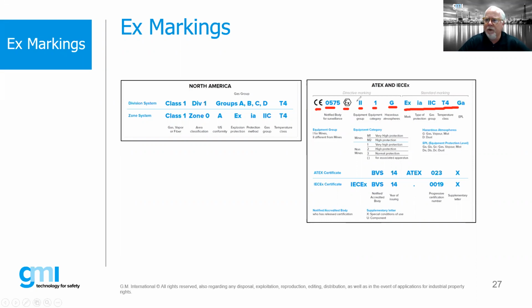So this is a typical marking string that we would find on a piece of equipment. And then what you will also find, you should find information, the certificate number. Generally, we see the term ATEX within the certificate. That's a dead giveaway that it's telling us it has an ATEX certificate. And then we'll also find, in many cases, an IEC-EX certificate as well. So that is what you would typically find with a lot of products.